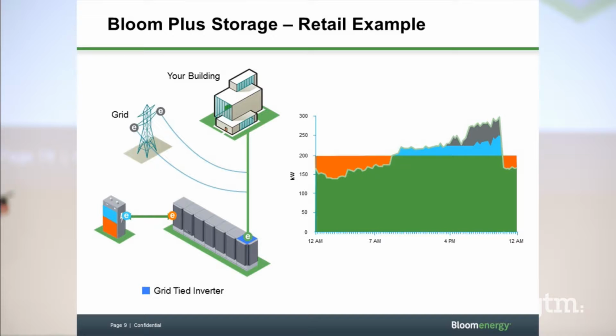Then you simply continue charging the battery as you shift back into nighttime hours. Now the devil's in the detail in terms of having the intelligence, looking at the seasonal data, etc., for these load curves. This is just a simplification of a load curve—you have to have daily load curves and match your solution to it. You have to size your battery solution and the Bloom solution so you can get this behavior in a consistent manner. But what you've essentially done is save them on almost all of their power costs.